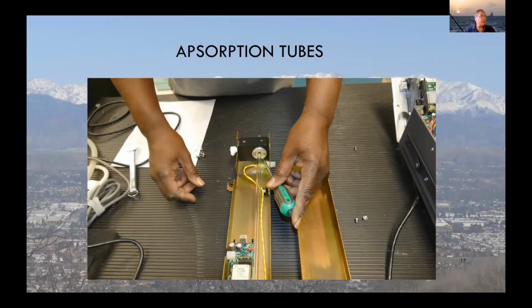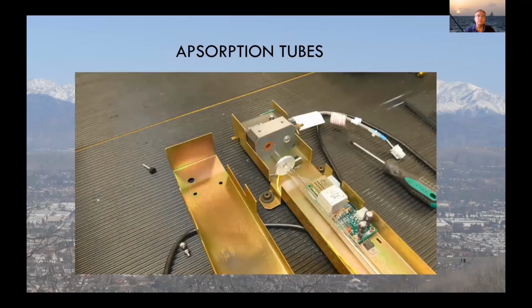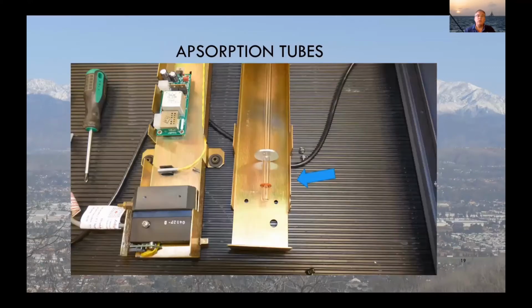So we've removed a sample bench from an ozone analyzer and placed it on a tabletop. And the technician here is going to remove the absorption tube from the sample bench. To do so, he's removed the 2 screws that hold the retaining ring on both sides. It's showing one of them pulled back. After you pull back both retaining rings, you can slide out the absorption tube.